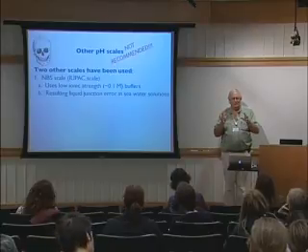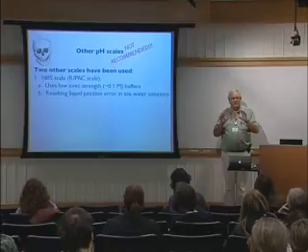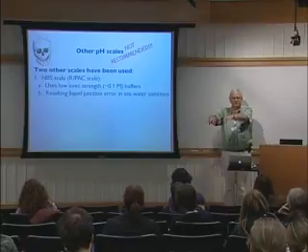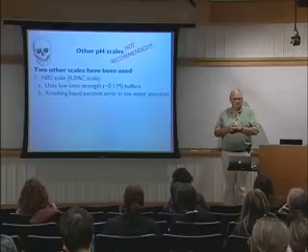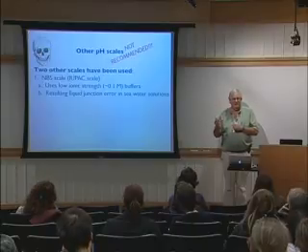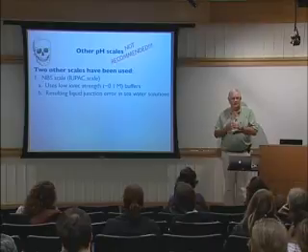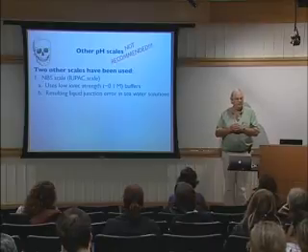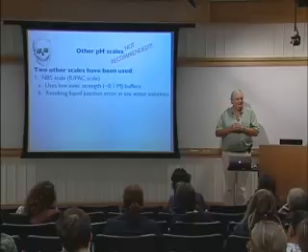So if you have 3 different designs of liquid junction and you put them all in the buffer and all in the seawater, you will get 3 different pHs. Very different? Mostly no, because most designs aren't that different. But some, the difference could be about 0.02 in pH, no trouble.